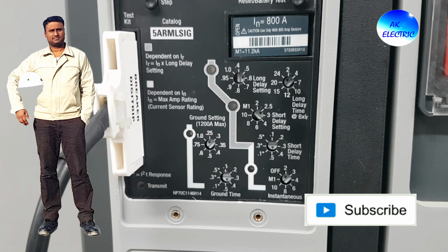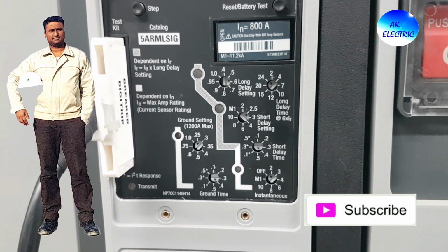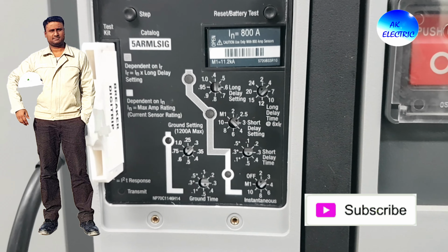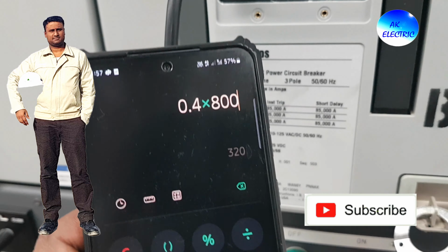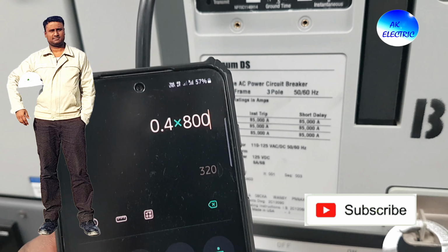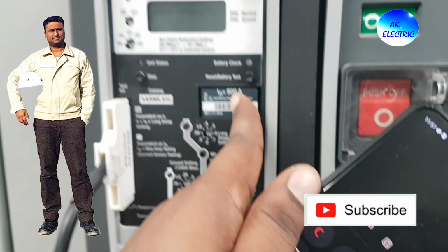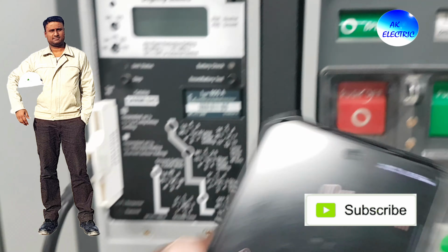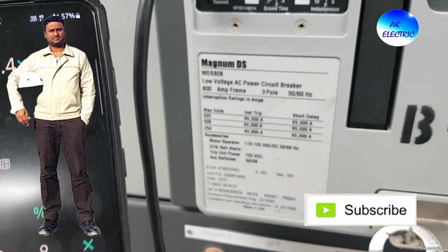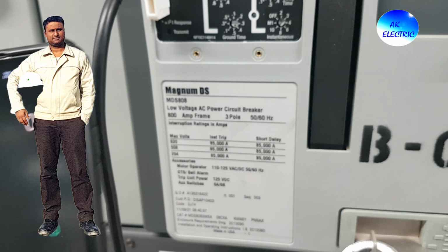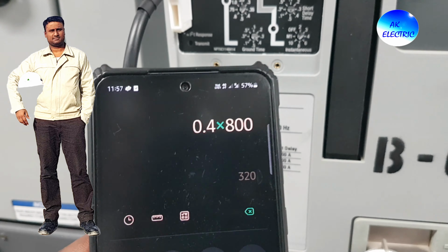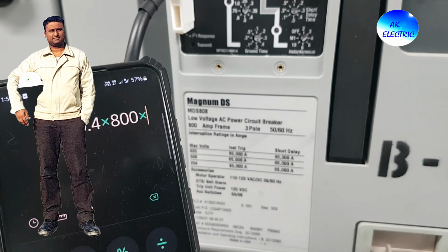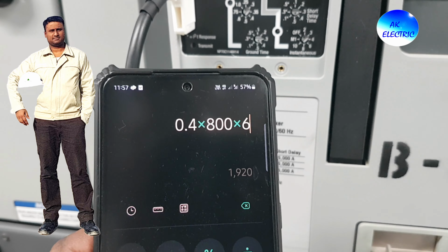So 0.4 into 800, this breaker rating, comes to 320 ampere. Our breaker rating is 800 ampere. So 0.4 into 800 gives 320, then times 6 you will get 1920.